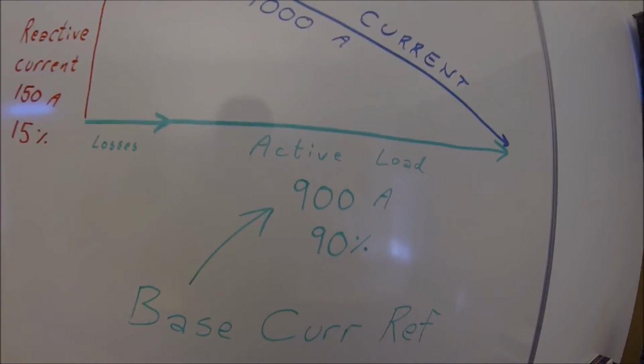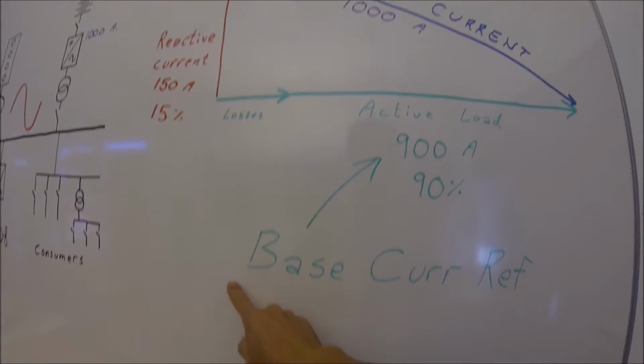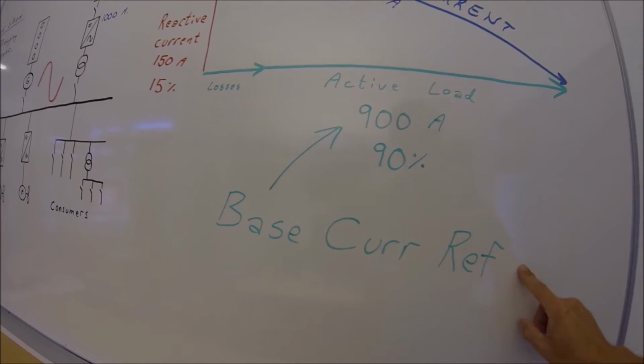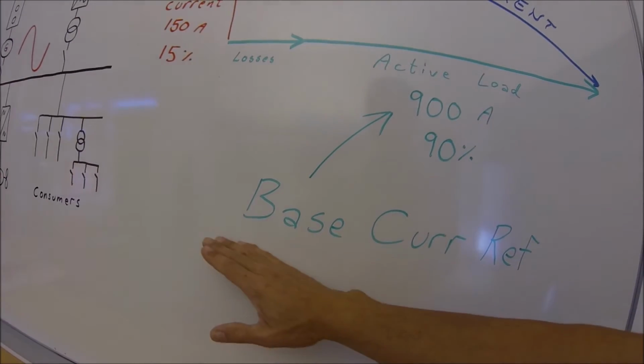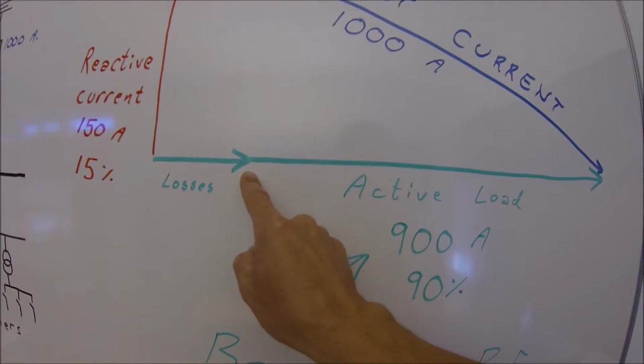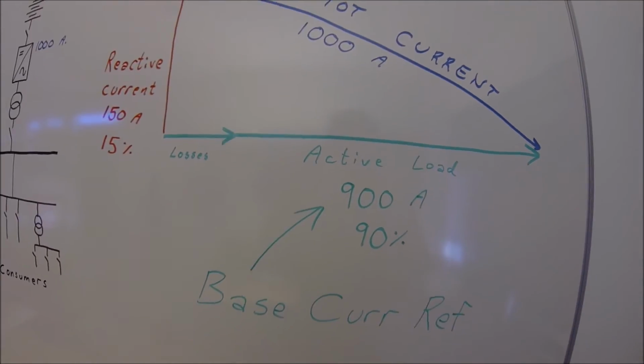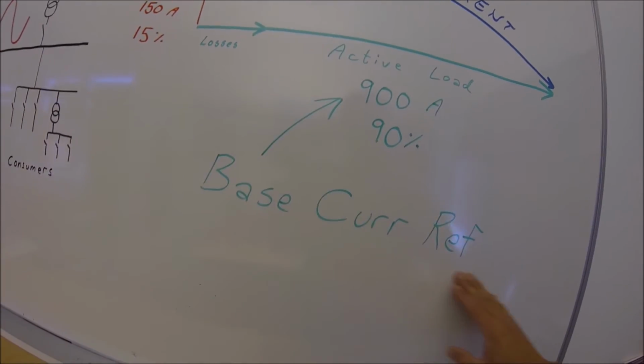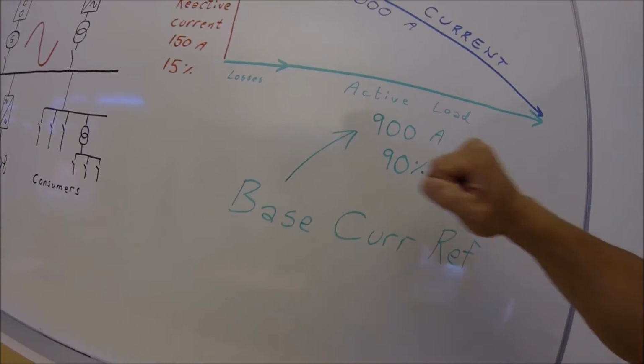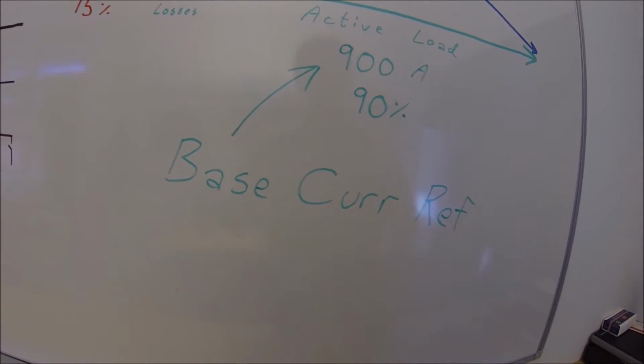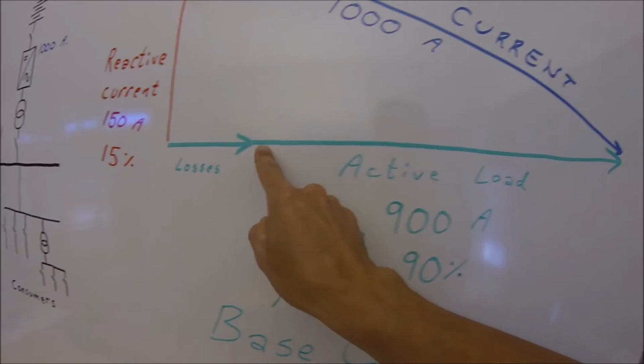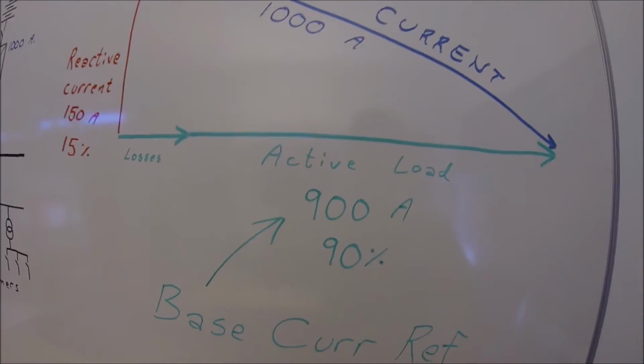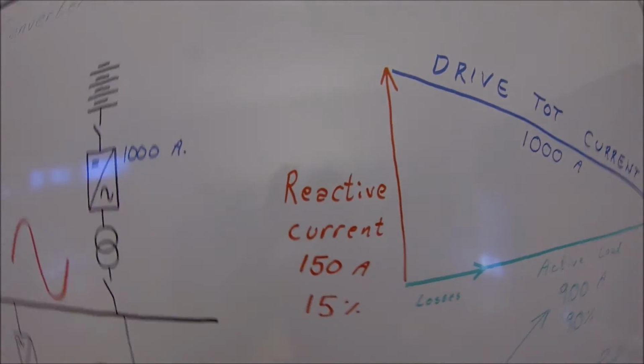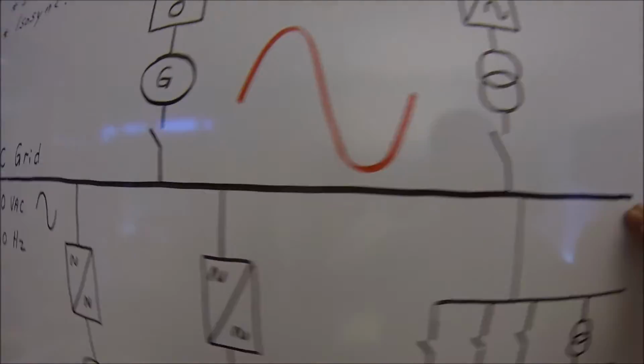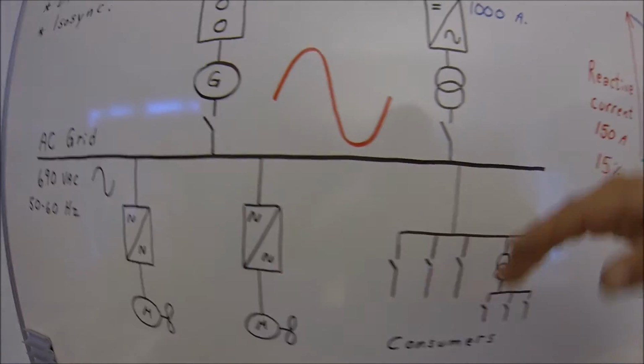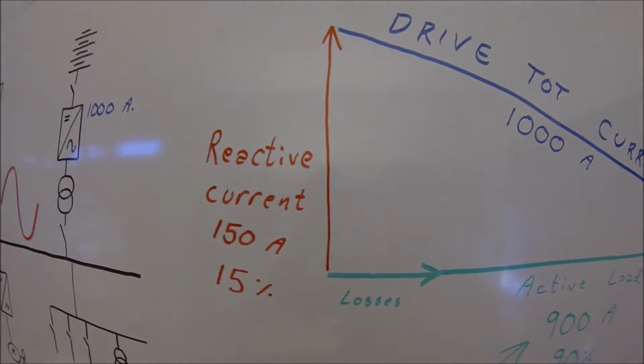Another thing is that the active load is the same as the base current reference given from the power management. It means if the power management asks for a specific active load, this is given on the base current reference. This is like the power handle from the power management to the drive, and it reflects only the active current. What the reactive current will be, you never know, because it's the voltage drooping on the grid. So you just have to leave some margin for it.